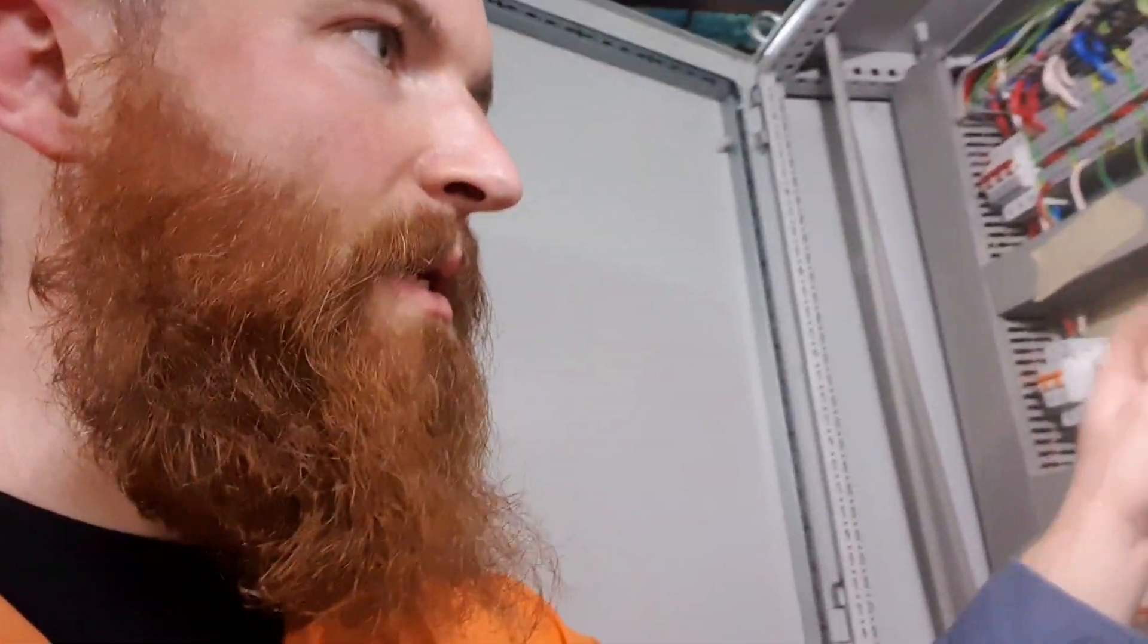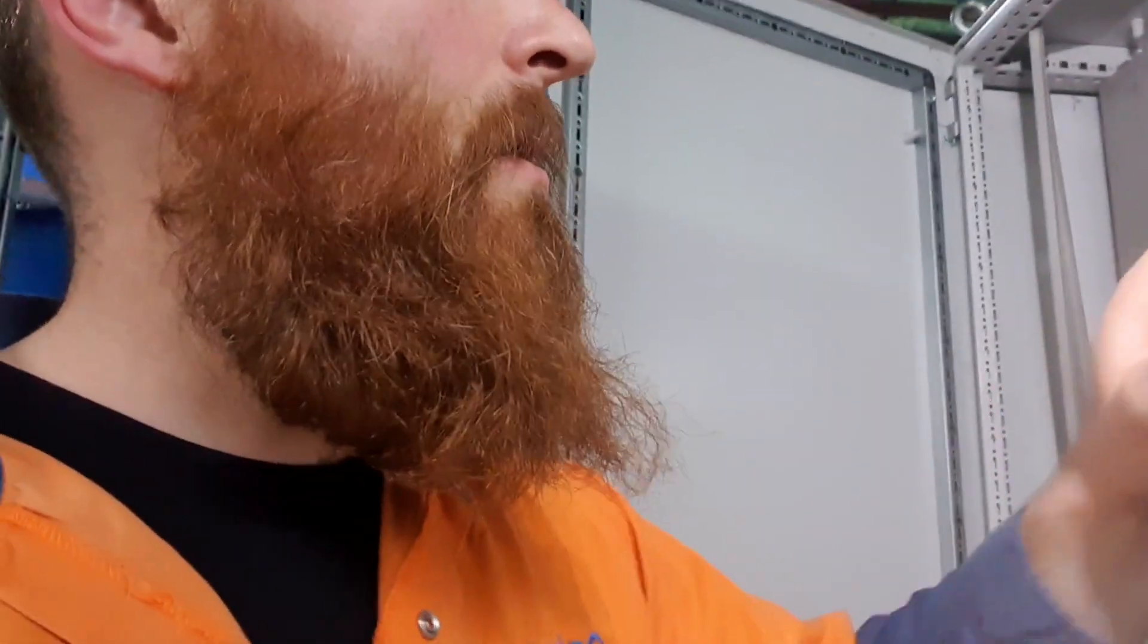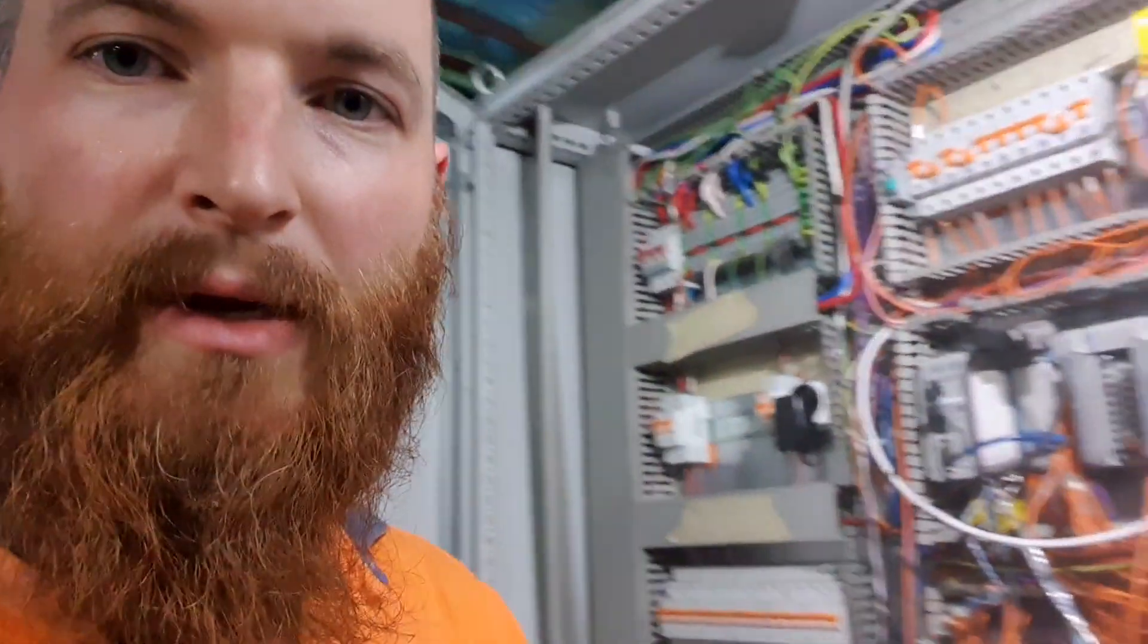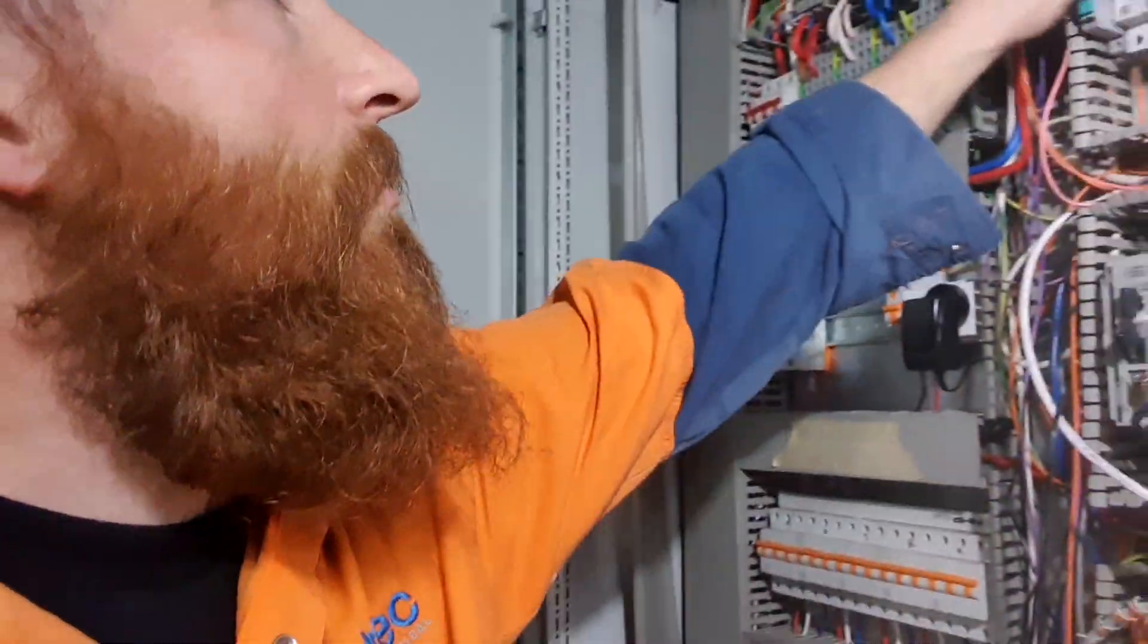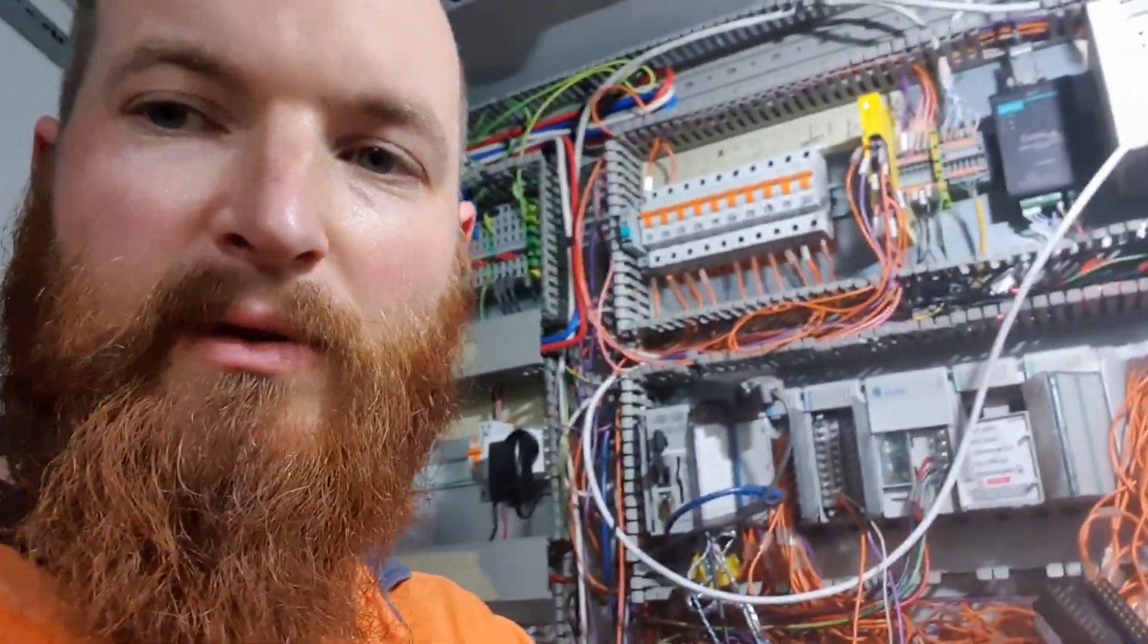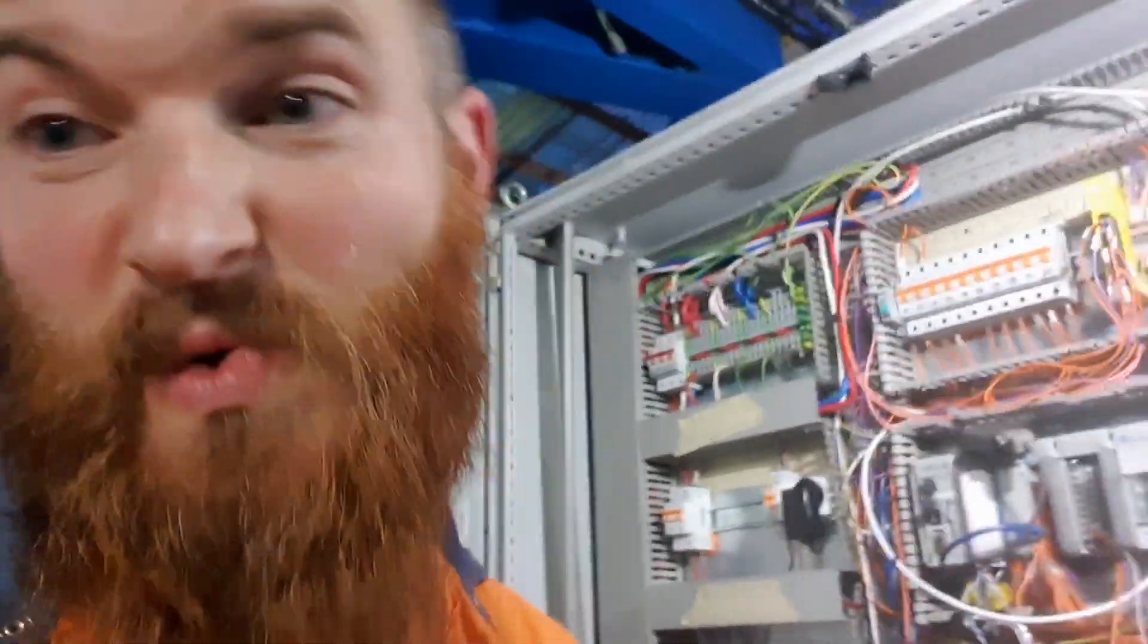There's another panel. You can probably see right there. That one's this power supply's daisy chained off. Anyway, long story short, after a little bit of mucking around, the phases, there's two dropped phases here. So I'm going to go and try and fix that in the main panel, which I've already been over there, but I'm just explaining the start of this job.